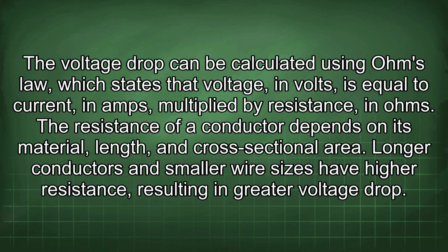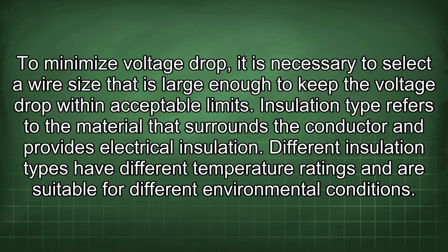The resistance of a conductor depends on its material, length, and cross-sectional area. Longer conductors and smaller wire sizes have higher resistance, resulting in greater voltage drop. To minimize voltage drop, it is necessary to select a wire size that is large enough to keep the voltage drop within acceptable limits. Insulation type refers to the material that surrounds the conductor and provides electrical insulation.